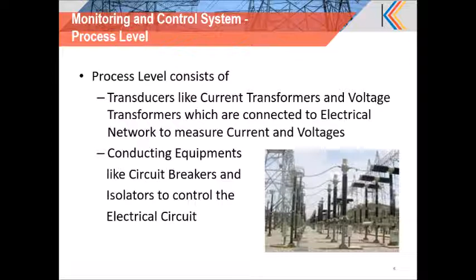So moving on to the different layers in detail. All HV equipment, the primary equipment, constitutes the process layer, which includes sensors, actuators, and other remote process interfaces. The bay level includes IEDs, relays, protection equipment, controllers, and other things. And the station level includes HMI, SCADA, and other functionality needed to be covered under the station level. Focusing on the process level, it includes different current transformers and voltage transformers, where electrical current and voltage measurement is the primary aim, and also conducting equipment like circuit breakers and isolators, closely connected to breaking the circuit or establishing the circuit back.